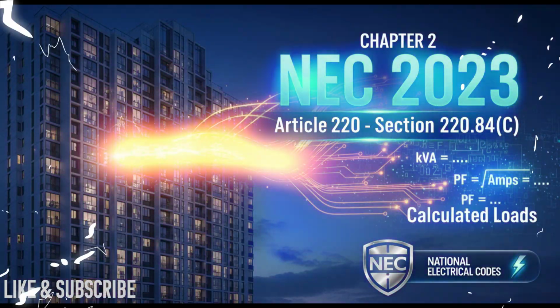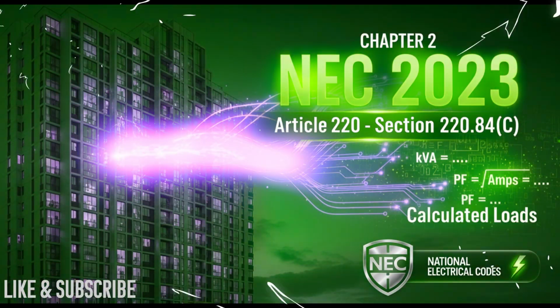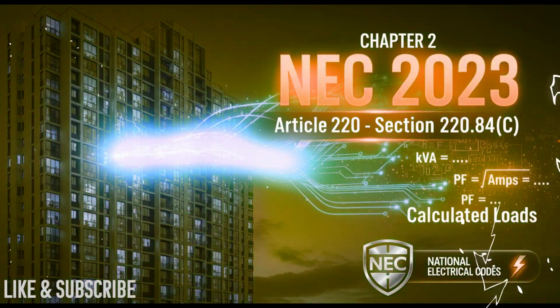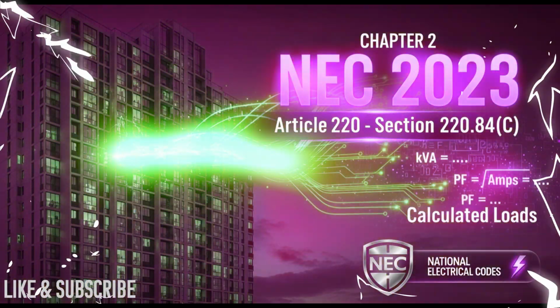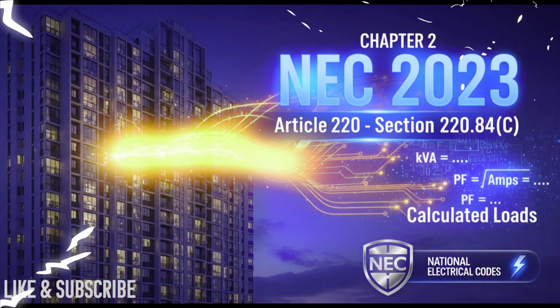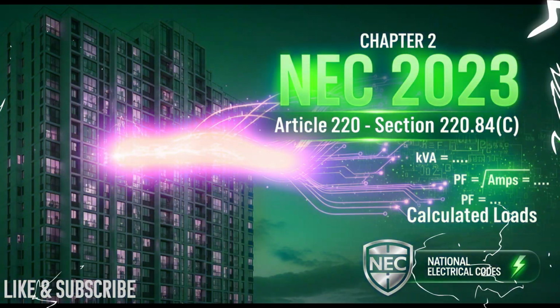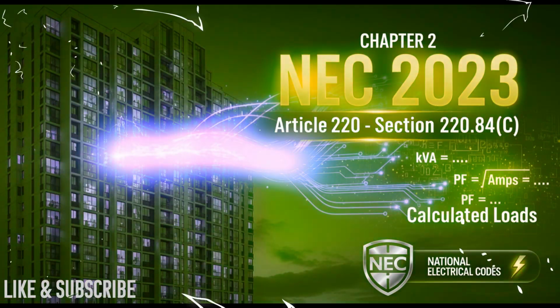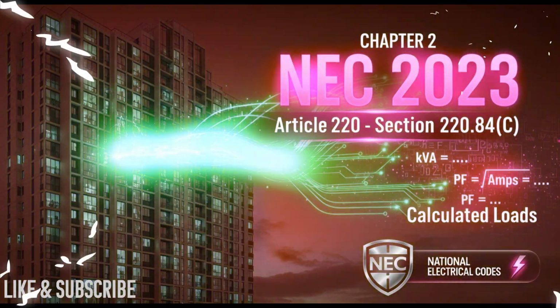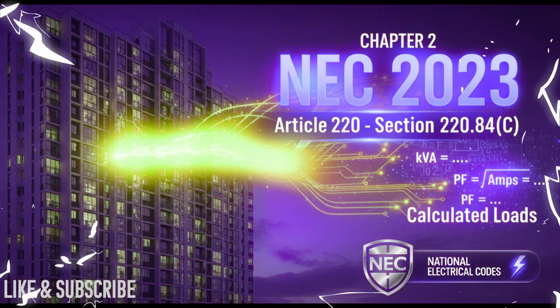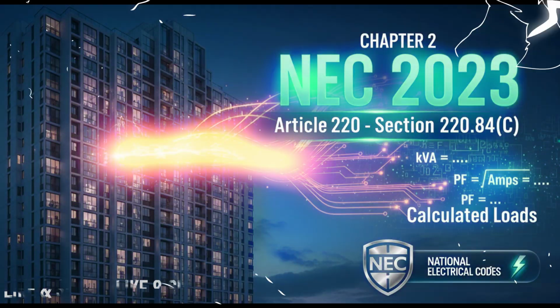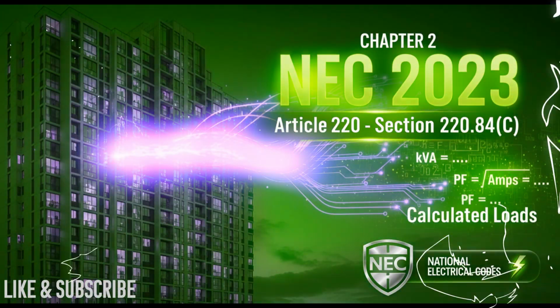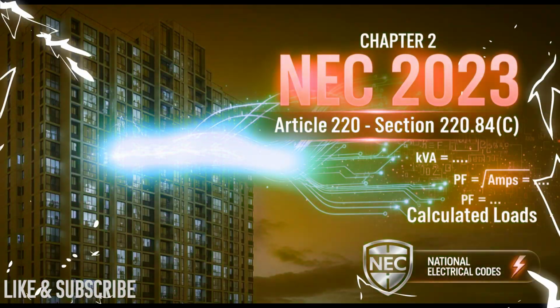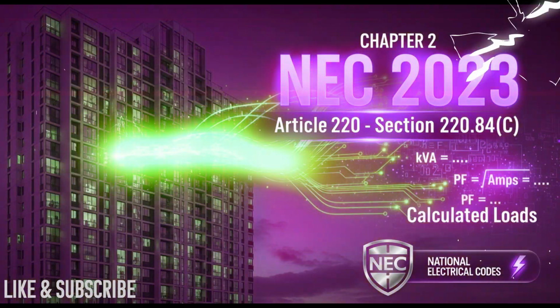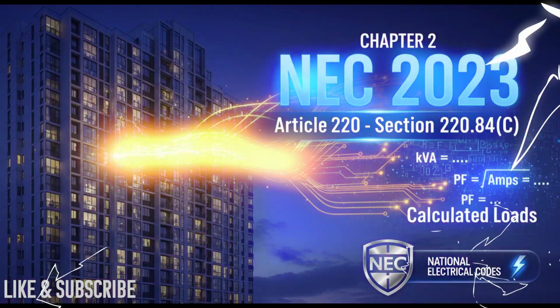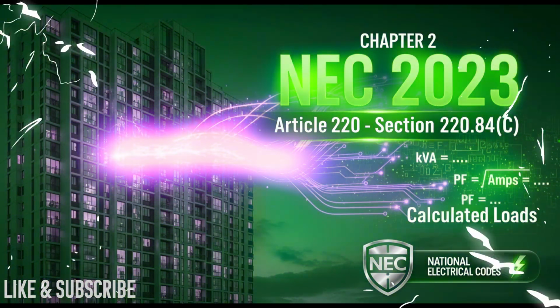What's input number 2? Input 2 covers those dedicated higher draw circuits you find in pretty much every unit: small appliances and laundry circuits. Kitchen counters, laundry room. Exactly. For this second piece, the code says you must add 1500 volt amperes for each required small appliance branch circuit in the kitchen. And you also have to add another 1500 volt amperes for each dedicated laundry branch circuit. Okay, let's translate that code speak. The references in the source, 210.11(C)(1) and (C)(2), those are the standard required circuits for kitchen counters and the washing machine hookup, right?